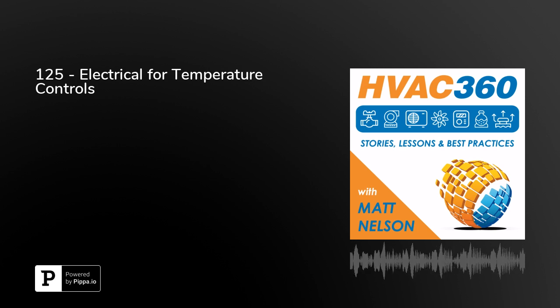You could also have transformers in VAV boxes. A lot of times if you have electrical heat in a VAV box, you're going to have a transformer right in that box. You might even have more than just 120 volts going to that box, depending on the size of the toaster coil that you have in there. So I just wanted to lay that out there. Those are some of the uses for your AC power, different spots that it's going to go to. I just want to keep it simple.